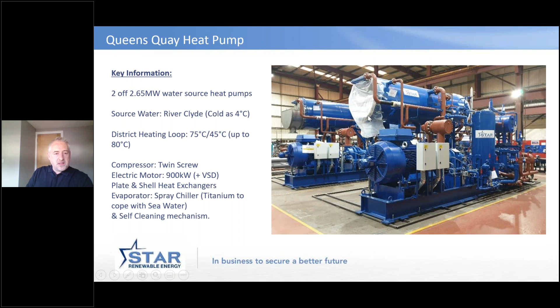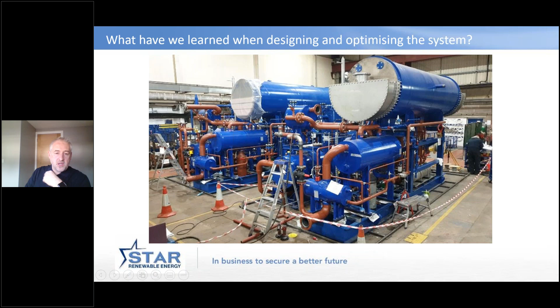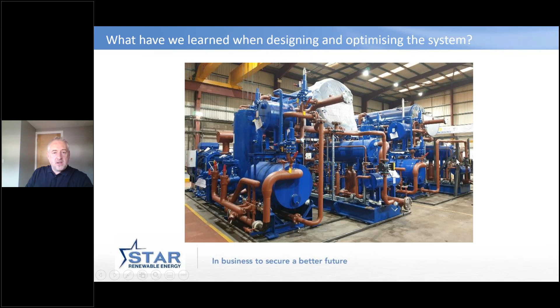So down the other end of the heat pumps, we've got the heat recovery part. So whilst the cold end, if you like, is quite important, the warm end is also, and you can see it looks quite busy. And the reason it's quite busy is because there's quite a few different places. So you can see up here is the desuperheater. So this is where we get the first chance to recover heat from the gas. Then still vapor, high pressure, goes across to the condenser, and we get probably about 80% of the heat out of the condenser, then into the subcooler. And also going on at the same time, we've got the oil cooler here, which is managing the oil temperature for the system to keep it running okay. So we'll pick through each of these and see why they're significant.